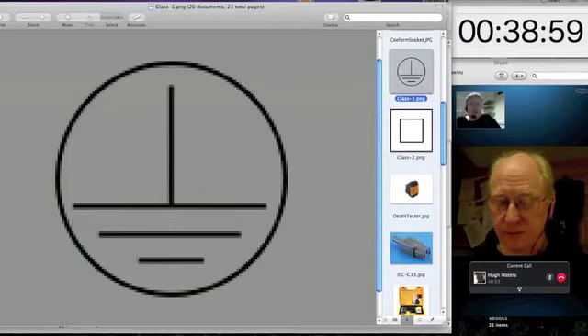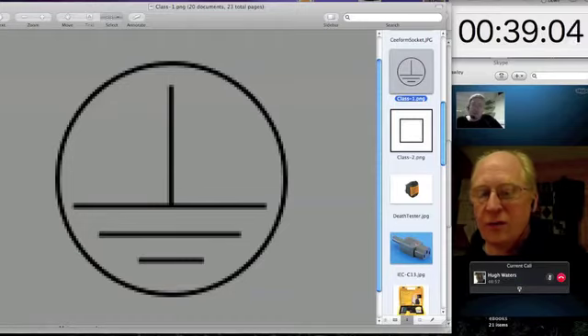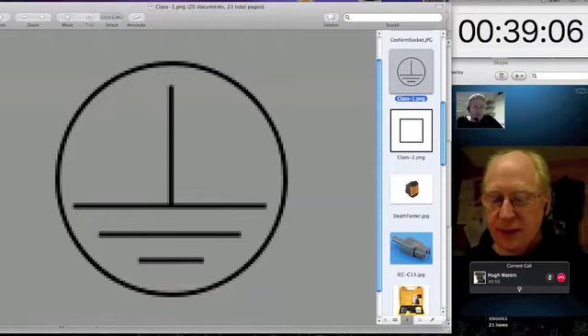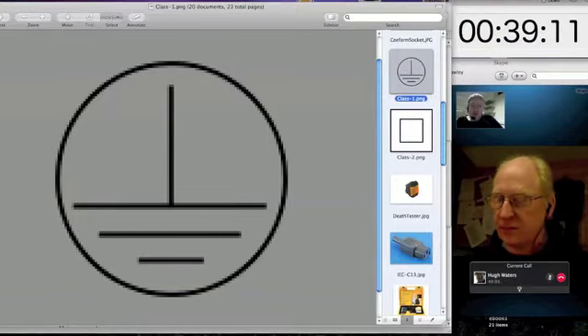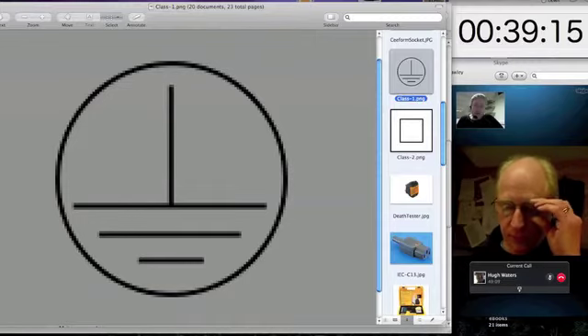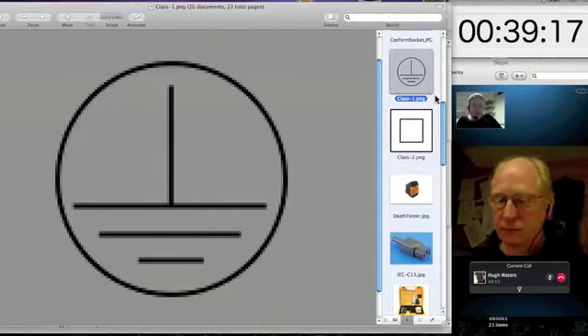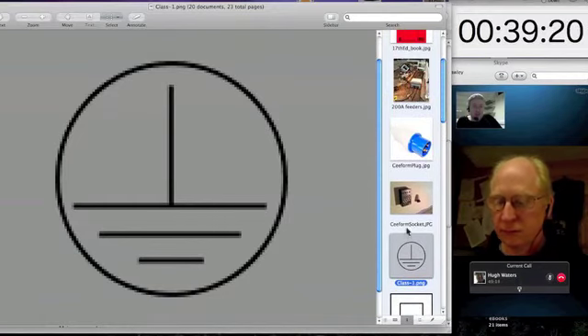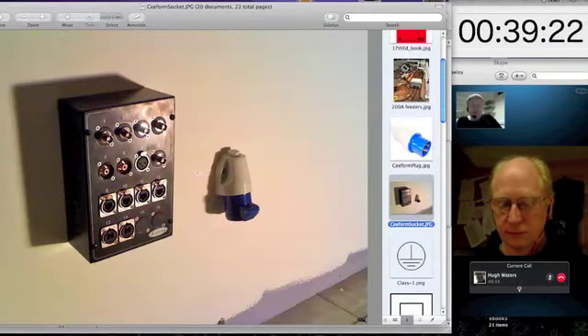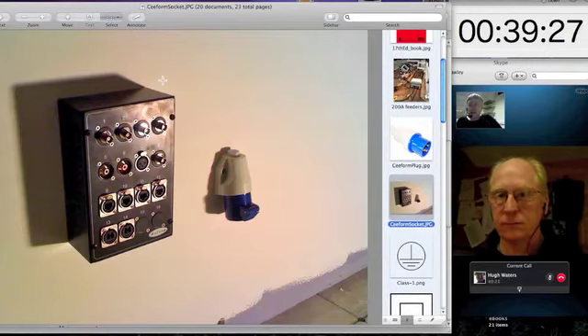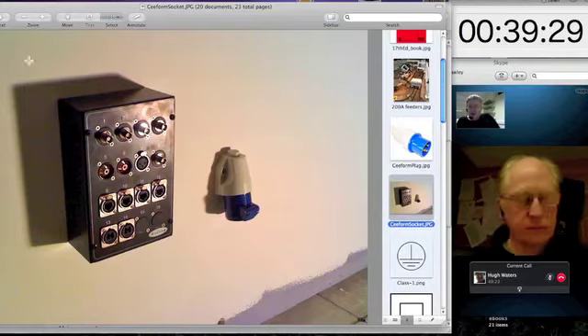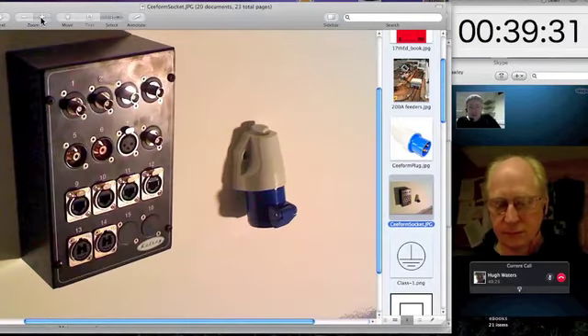Okay. So just a bit of a recap of what I normally specify as the optimal configuration for edit suites, and that's knowing that I've got the same technical earth feeding my machine room cabinets as is feeding the technical outlet in the edit suites. Because if, for example, I had my machine room done correctly and I had just any old kind of earth from another supply in my edit suites, that's when you run into trouble.